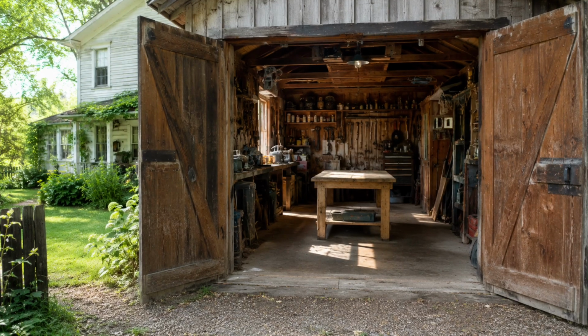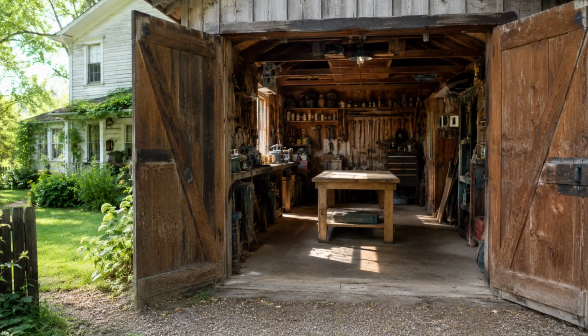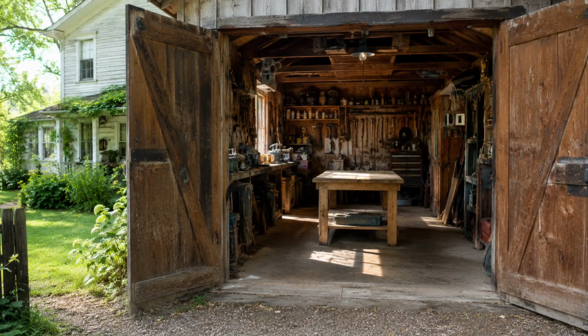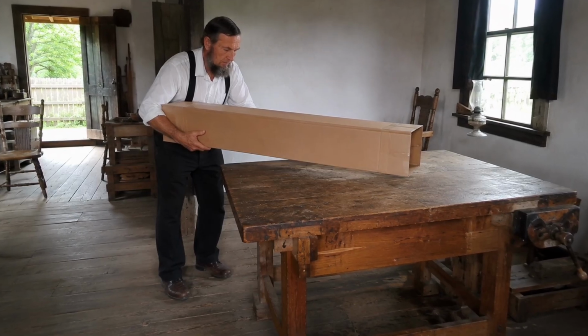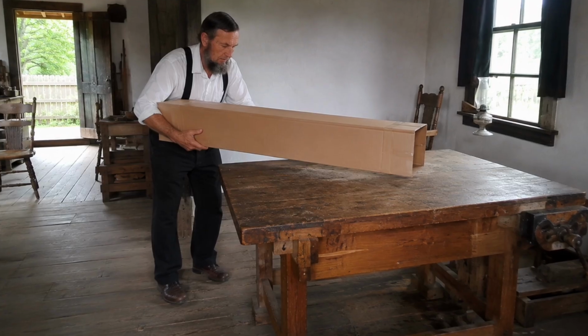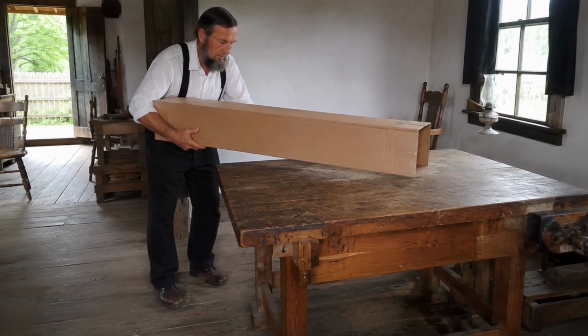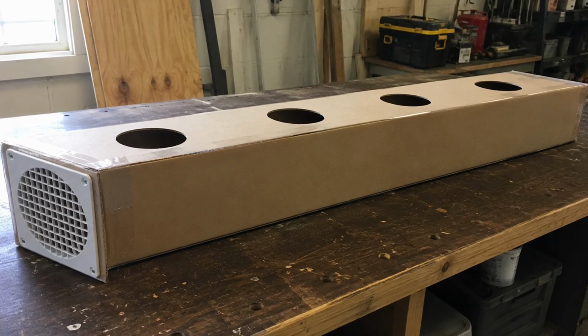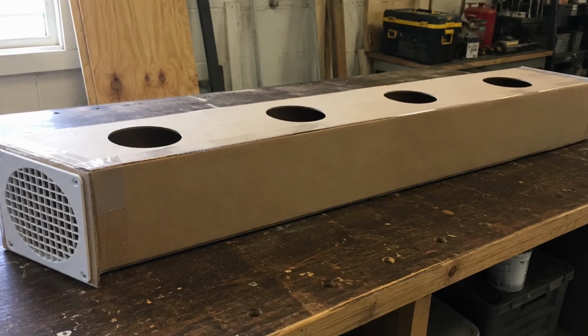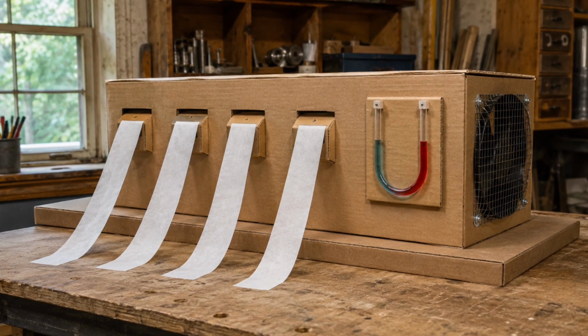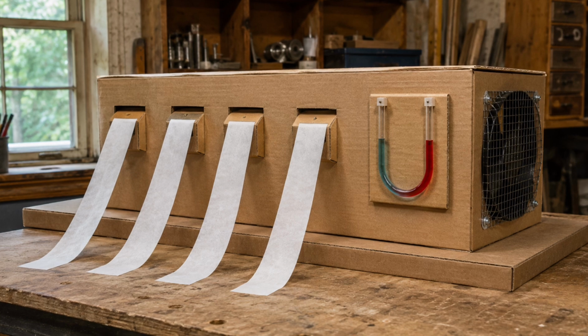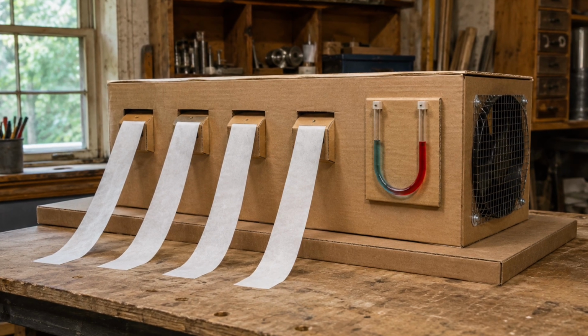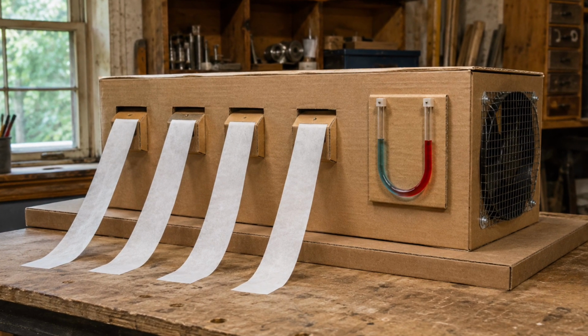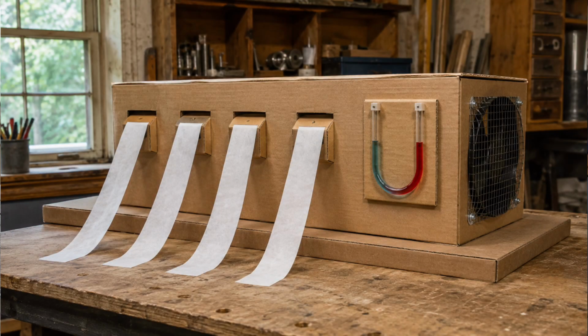I built the whole argument small enough for a bench, and I want you to watch it happen. Here is a box duct made from cardboard and tape, with one small fan pushing air in at one end and 4 outlet holes along the top. Those are my 4 rooms. Over every hole I have taped a light paper streamer so the air can show itself. I have also fitted a simple clear tube pressure gauge near the fan. It is not a calibrated test of your house. It is a model that lets us see what restriction does.